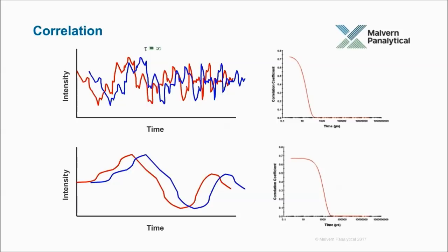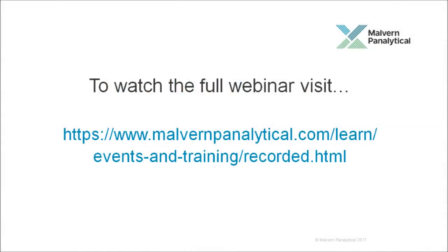So this, fundamentally, is what we get from a DLS measurement. We call this the correlation function, or correlogram, or autocorrelation function. And what we're observing here on the y-axis is the correlation coefficient, the similarity of the signal with respect to itself, plotted as a function of delay time. And you can now see on this x-axis, we are covering a wide range of delay times. We're starting at 500 nanoseconds, or half a microsecond, and we're going all the way up to a couple of seconds in delay time. In this upper signal, we can see that this loss in correlation is occurring over quite short delay times. Typically, in this example, over a few microseconds. In the bottom signal, however, the correlation persists for longer. And we don't really start to see a loss in correlation until we're up to a few hundred microseconds in this example.